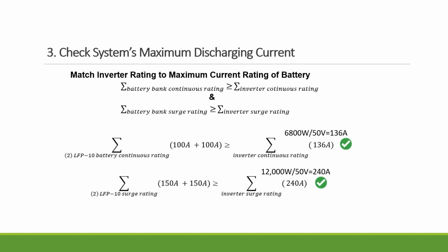Okay, and then the third step is to check the system's maximum discharging current. You need to check the inverter's continuous rating as well as the surge rating, and make sure that rating is equal to or smaller than the battery bank's continuous rating and surge rating. For instance, in this case with two of the LFP-10, they allow you to discharge 200 amps because you put them in parallel, doubling the maximum discharging amperage. In this case, it is 200 amps.